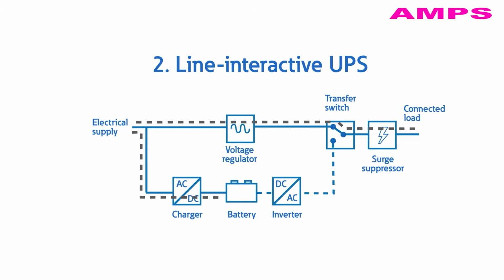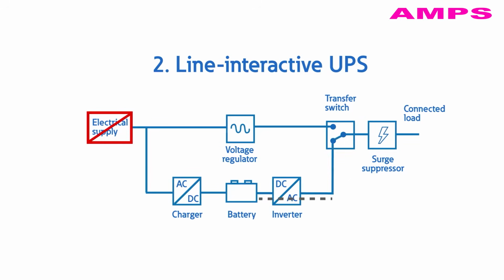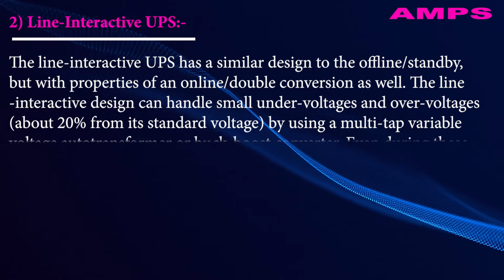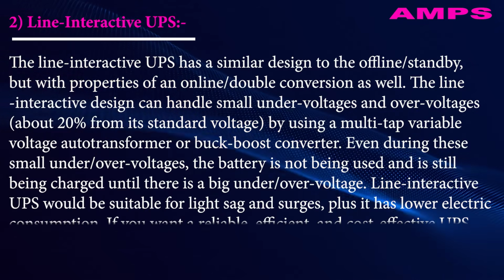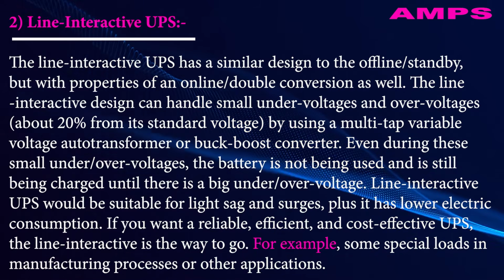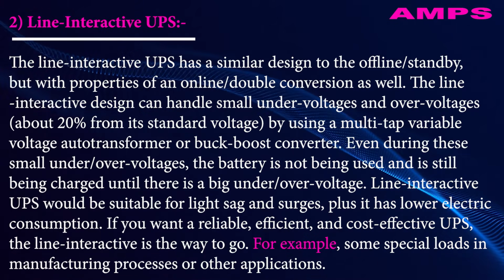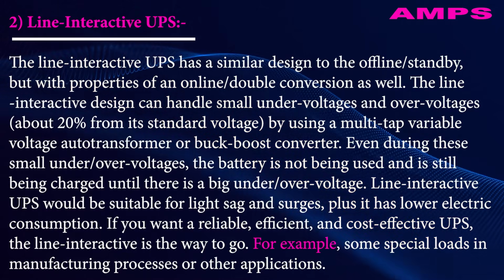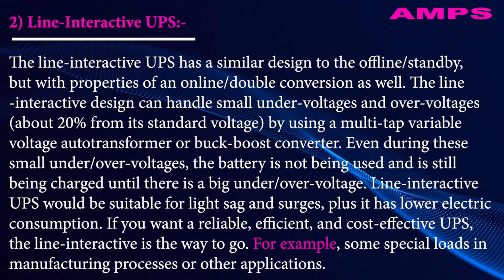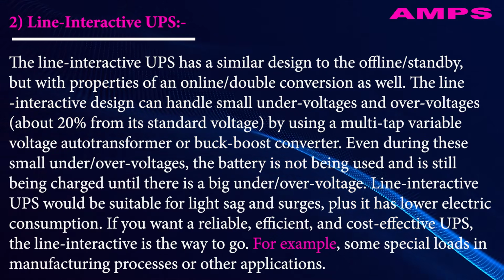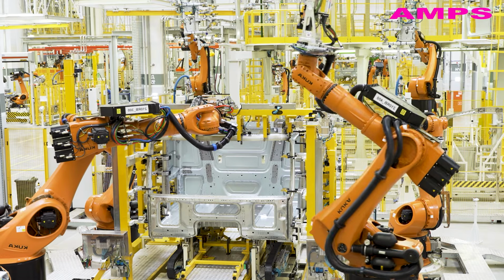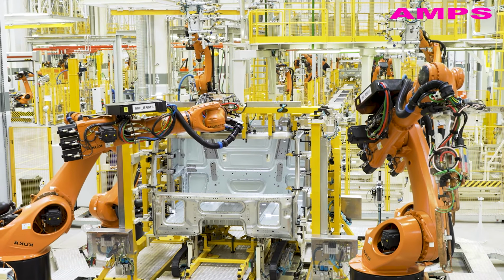The line interactive UPS has a similar design to the offline or standby, but with properties of an online/double conversion as well. The line interactive design can handle small undervoltages and overvoltages, about 20% from its standard voltage, by using a multi-tap variable voltage auto transformer or buck boost converter. Even during these small under or over voltages, the battery is not being used and is still being charged until there is a big under/over voltage. Line interactive UPS would be suitable for light sag and surges, plus it has lower electric consumption. If you want a reliable, efficient, and cost-effective UPS, the line interactive is the way to go. For example, some special loads in manufacturing processes or other applications.